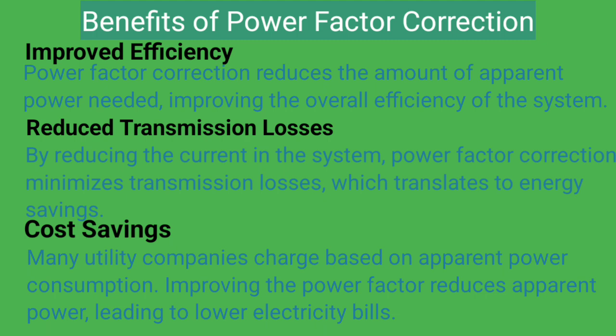Benefits of power factor correction. Improved efficiency. Power factor correction reduces the amount of apparent power needed, improving the overall efficiency of the system. Reduced transmission losses. By reducing the current in the system, power factor correction minimizes transmission losses, which translates to energy savings. Cost savings. Many utility companies charge based on apparent power consumption. Improving the power factor reduces apparent power, leading to lower electricity bills.